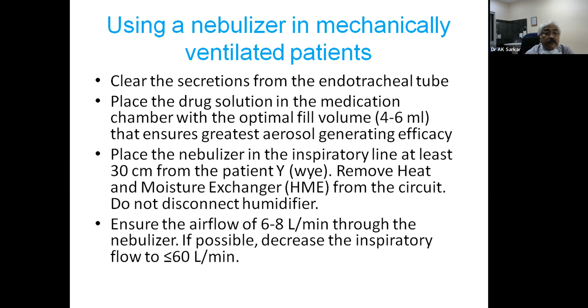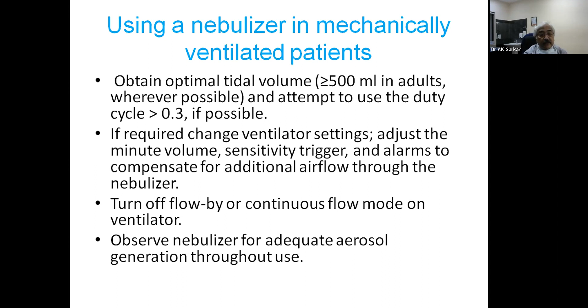Then you adjust your ventilator. Whatever mode he is in, it should go to volume control mode, and your tidal volume should be around 500 or above, and the inspiratory expiratory ratio should be 1:3, or your inspiratory time can be more than that. And if required, you change the ventilator settings, because you need to adjust the minute volume and sensitivity trigger. Otherwise, there will always be an alarm whenever you are using a jet nebulizer, because it interferes with the ventilator settings. If it is a continuous flow, then you turn it off to intermittent flow, and always observe the nebulizer, whether it's generating adequate aerosol or not. If not, you need to tap the nebulizer intermittently during operation, so that the nebulizer begins to sputter again.